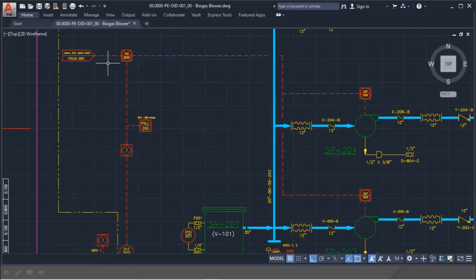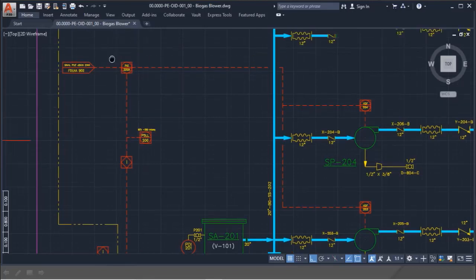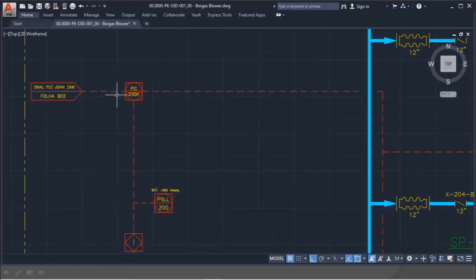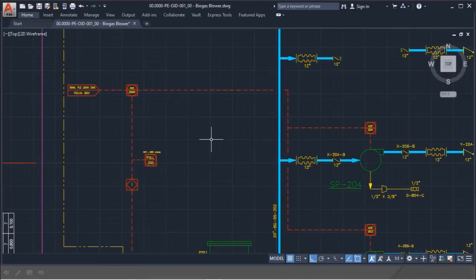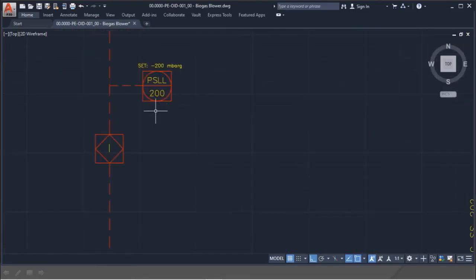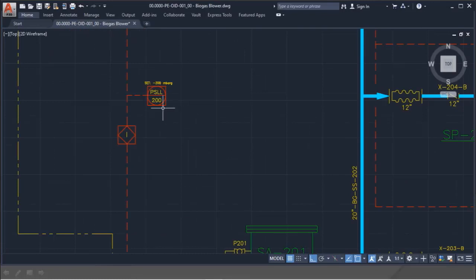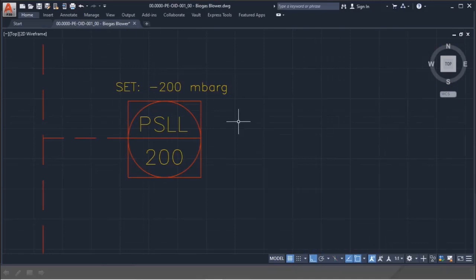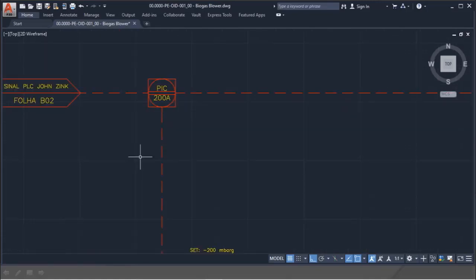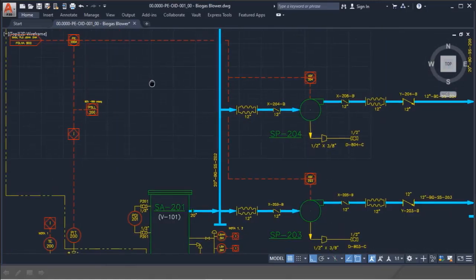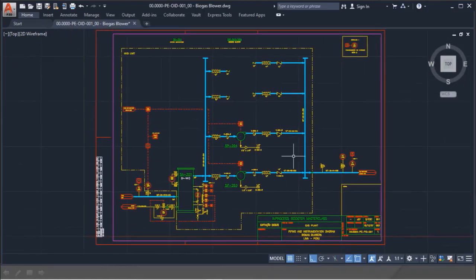There is also a signal here from another part of the process, and it means that there is a selector in this controller. It is not clear what kind of selector it is, but for our scope of supply, it doesn't matter. Observe also that we have a PSLL. It means if the suction pressure reaches minus 200 millibar G, the plant will shut down to prevent air entrance. So this is the main view or overview of the system based on the P&ID.